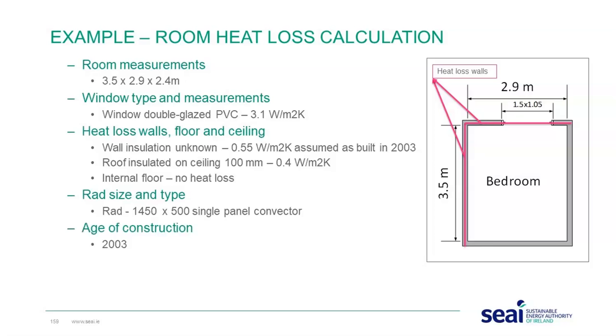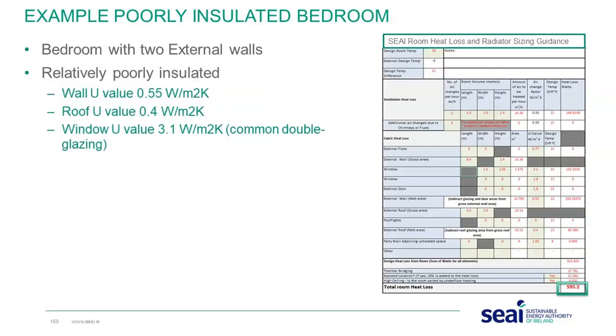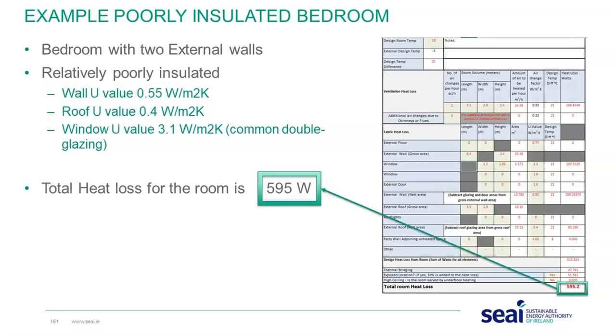And then the age of construction can be important as well, because we might not always know what the U values are. So again, going back to the SEAI room heat loss and radiator sizing guidance, there's a tab there where you can fill in all the details. I have an example here, and I've taken the bedroom, and in this scenario, it's relatively poorly insulated. So the wall U value is 0.55, the roof U value is 0.4, and the window U value is 3.1. And you can see at the end, that will give us, when we fill in all the different factors, there are other factors there as well, so it'll be self-explanatory as you go to do it.